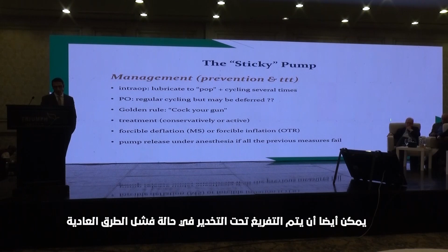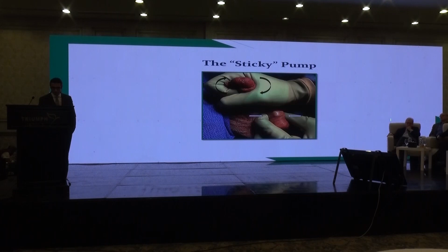So as I mentioned, treatment could be conservative, could be active. In case of conservative, there are examples like the momentary squeeze, forcible deflation, and I'll show in a picture afterwards, or forcible inflation in case of the one-touch release pump. Pump release can also be done under anesthesia if you fail all the previous measures. Here's an example of the forcible deflation, where you squeeze the shaft of the penis while pressing on the deflation button. In the case of a one-touch release, you try to maintain a good angle or straighten the exit tubing from the cylinders while forcibly pressing on the pump instead of deflation in this case.